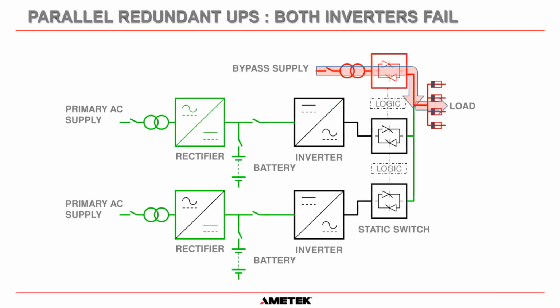And then in that circumstance, if the same happened to both UPSs, okay, or if the inverter then failed in that UPS, only then will the bypass supply come into action, okay? We only use bypass in a parallel redundant UPS when the output from both inverters into their static switches fail. The logic will detect it. It will immediately switch on the bypass static switch, and the loads will be powered this way. Okay, that will be off, and that will be off. So that is a parallel redundant UPS when both inverters fail.